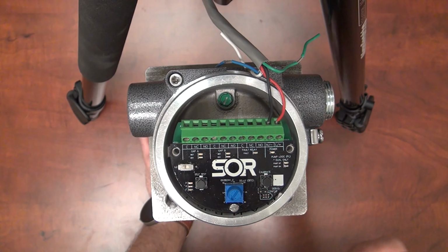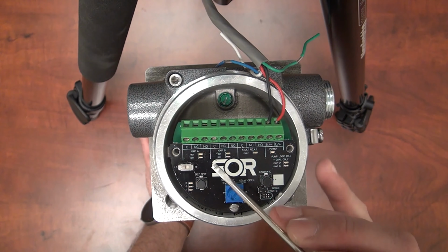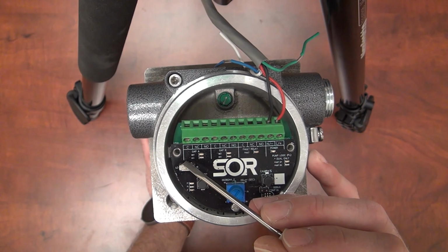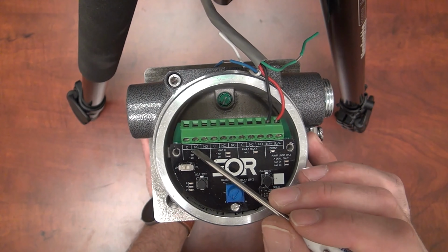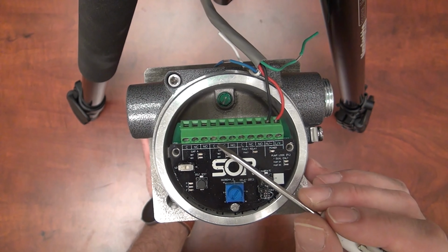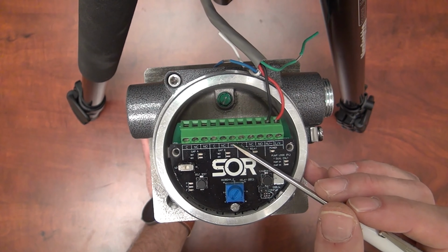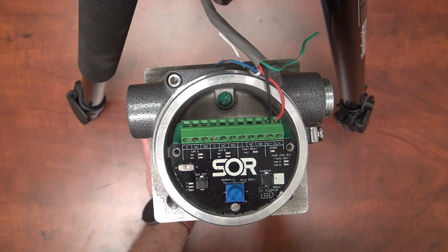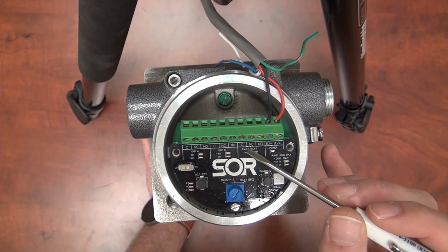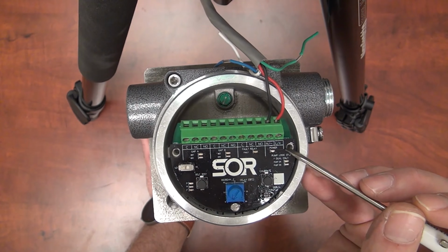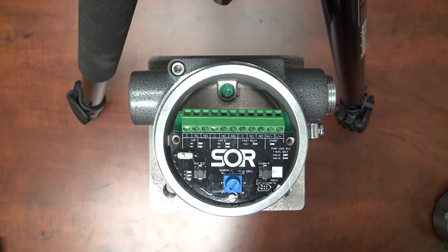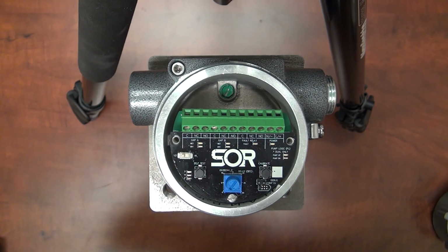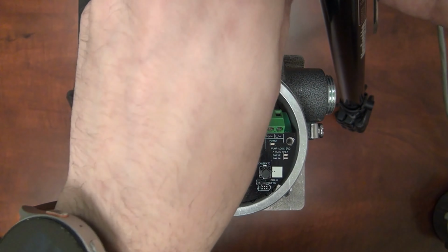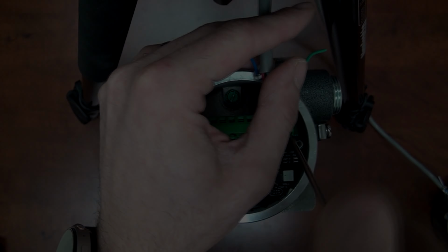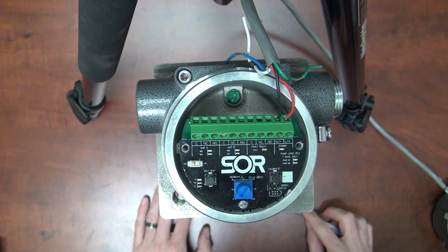At the top of each interface board is an 11-position terminal strip. Labels are printed directly onto the interface board. Here, these three correspond to gap A. These three correspond to gap B. Do note that single point units will not use gap B. Next, these three are for our fault relay, and these last two are for power. Unscrew the terminals and provide power to the device. Note, ensure that you are providing the correct power based on what is shown on the nameplate rating. And now with our power wired, we are ready to boot up the device.